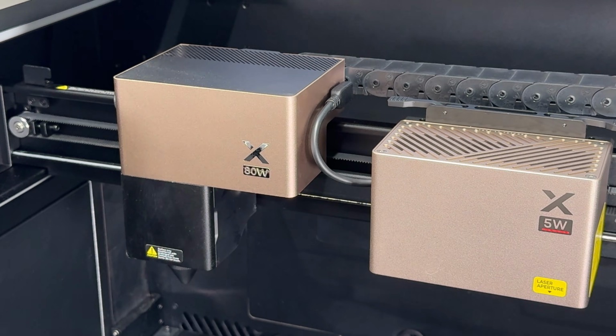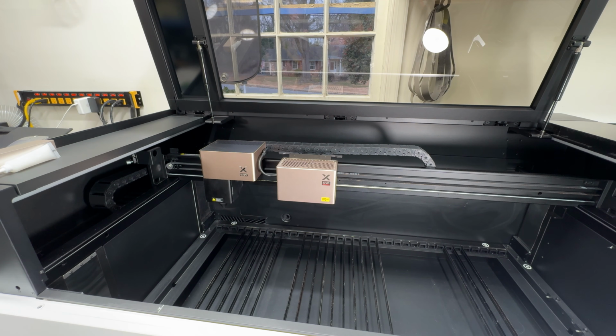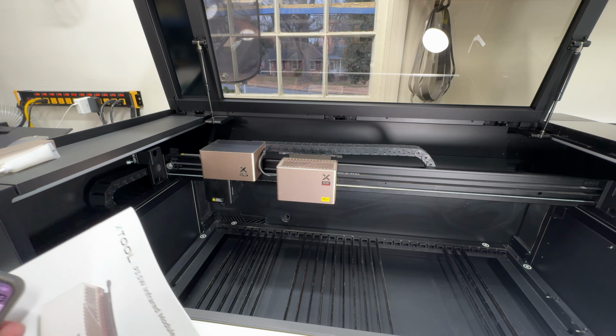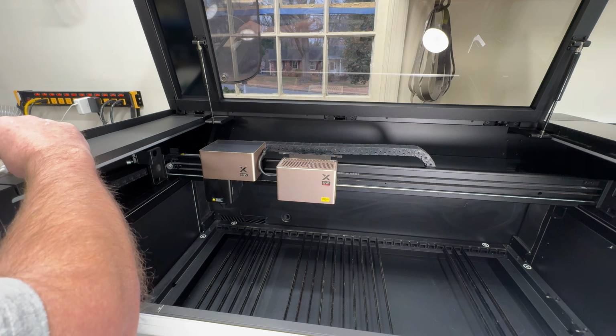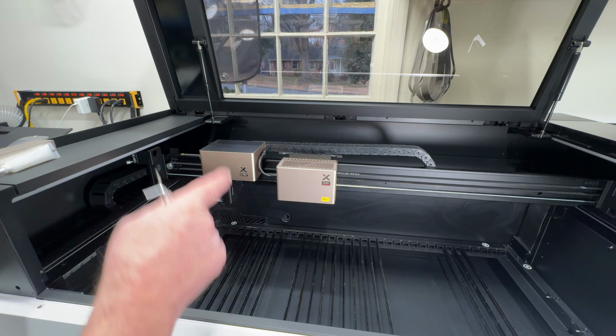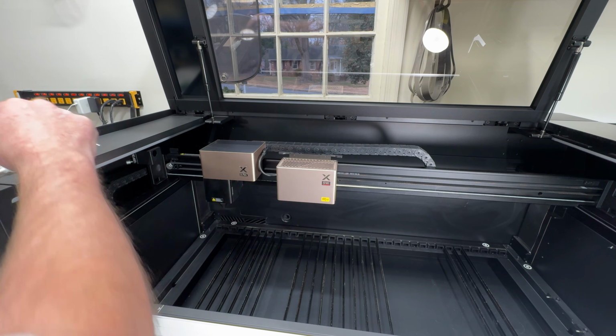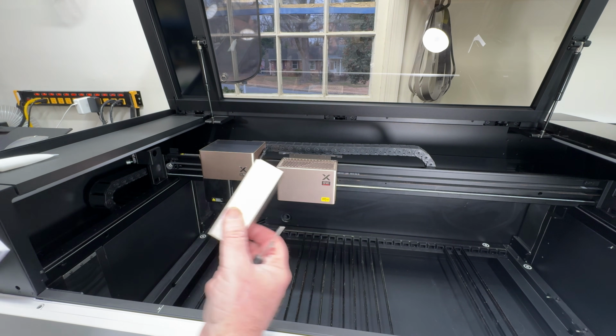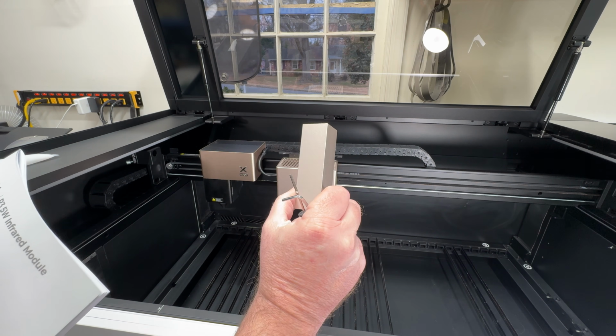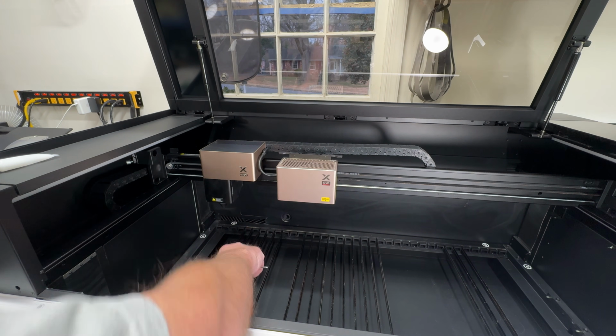Okay, next part. All right, we're all done with the inside installation except for doing a calibration test. So that's what we're going to do next. We're going to fire up the machine, make sure that the module gets detected. Then we're going to be using this, which is the laser calibration piece, for the test.